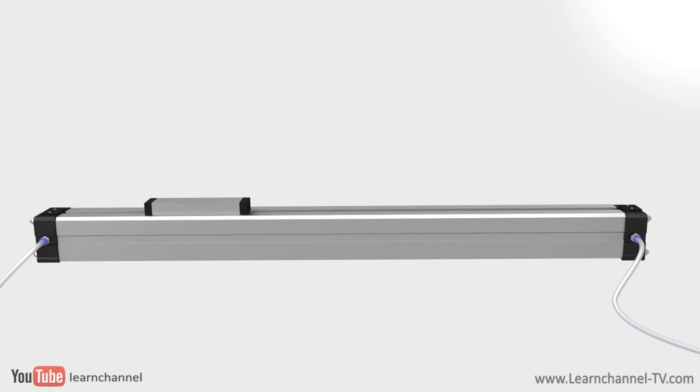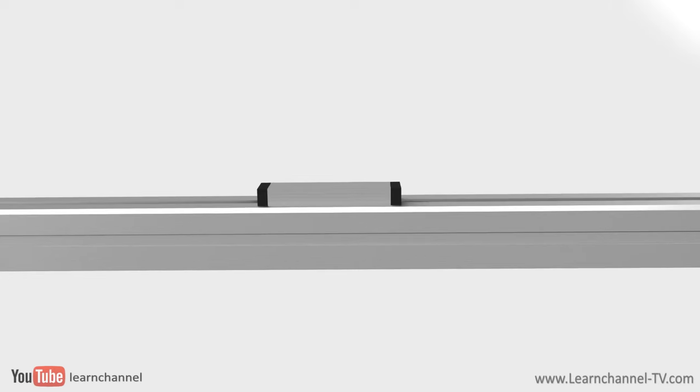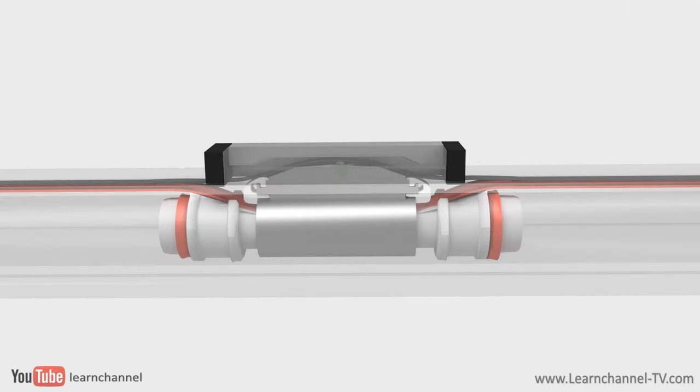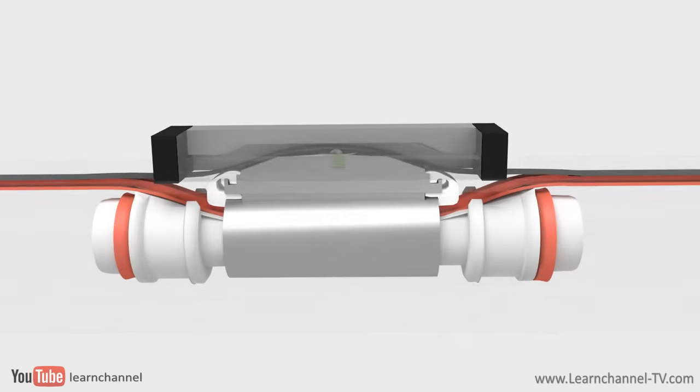If you want a rodless cylinder with a high cylinder force, you would choose a slotted rodless cylinder. Here, the piston is mechanically coupled to the carrier. An inner and outer band keeps the air within the barrel of the cylinder.